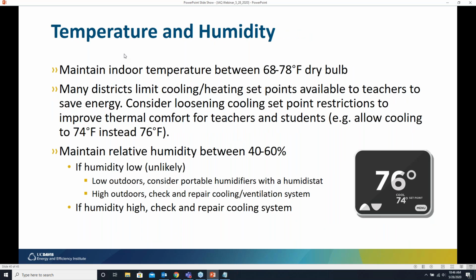Also wanted to just have a note about maintaining temperature and humidity in your spaces. Maintain temperatures recommended by ASHRAE of 68 to 78 degrees Fahrenheit. I did want to recommend that, generally speaking, districts limit cooling and heating set points to teachers to save energy, which is great. Considering our current situation, you might want to consider allowing teachers to have a little bit more control over their cooling set points, because often that's the biggest complaint in classrooms.